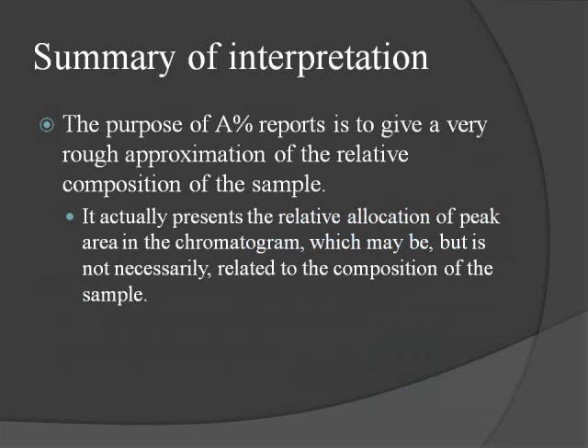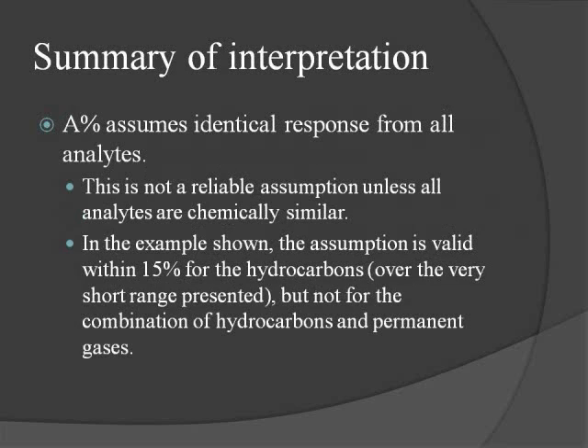Although it is widely thought that area percent is an approximation of the relative composition of the sample, it's actually a representation of the relative allocation of peak area. This relative allocation may be, but it isn't necessarily related to the composition of the sample. Remember the pitfalls involved in area percent analysis. It assumes identical response from all of the analytes in the sample. This isn't a reliable assumption.